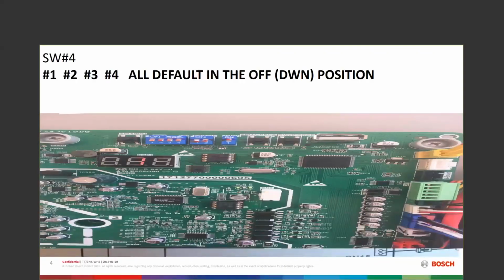So SW1 is that particular switch. SW4 is similar, but it has a little bit of a differential in that I get to use this board for the IDP, which is a package unit. This particular system on the 2.0, I get to separate my condensing unit from the air handler, whether it's yours or mine, or whether it's a case coil, whether it's yours or mine. But I get to separate those via refrigerant lines, and I get to stretch them to 150 feet. So the 1.0 was 100 feet. Now I get to move those to 150 feet. But the board is the same from this split system unit to the IDP unit. So we have to make sure that we have some different logics behind that. And in that particular logic, SW41 is going to have some characteristics to it that basically make this unit a split system and not the package unit.